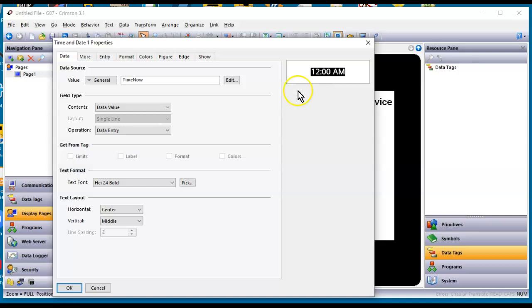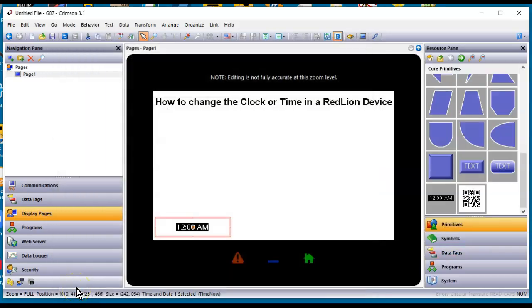So if I go ahead and use this and click the OK button and of course download this to the RedLion unit, this now is a field that you could edit on that RedLion HMI or device via the web browser or the actual HMI in front of you there. So you could actually put that on a settings page and you could adjust that any time. So say three months from now your clock's off by a minute or something for some odd reason, you can click on that and adjust the time on the fly without having to use Crimson. So there you can put a time primitive on the display page.